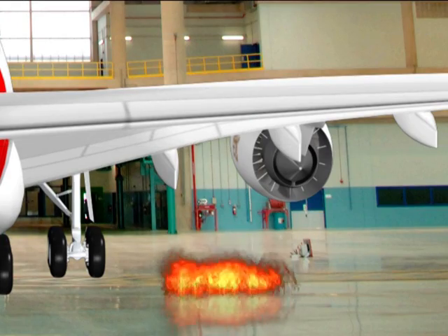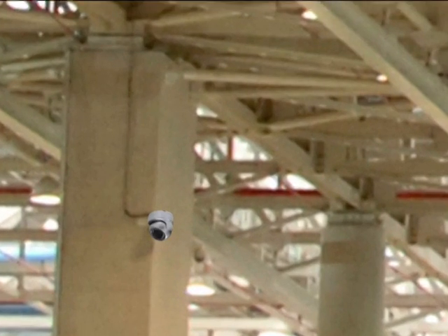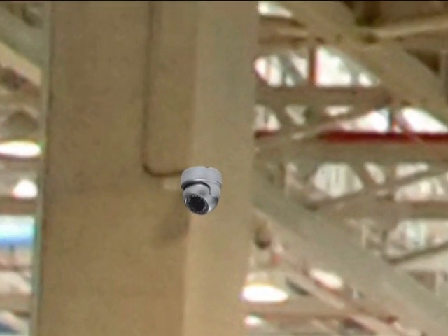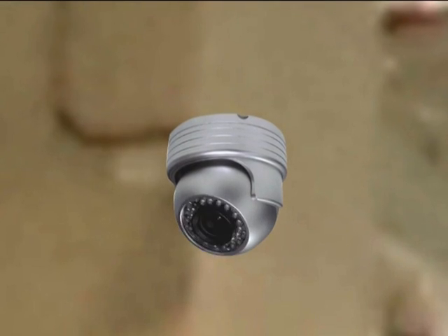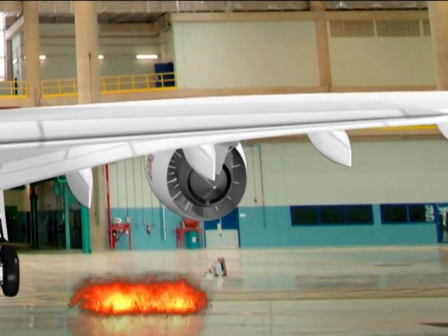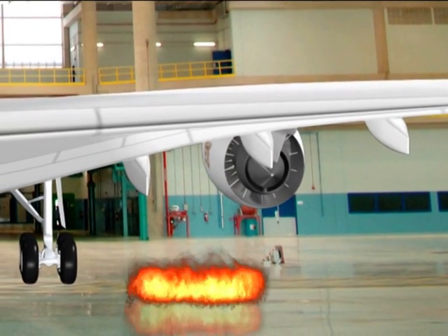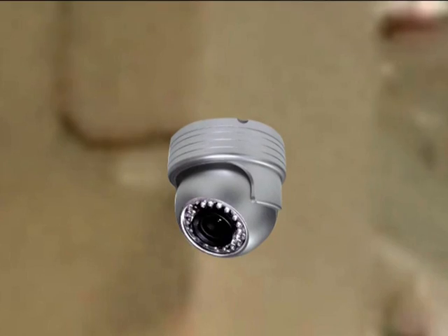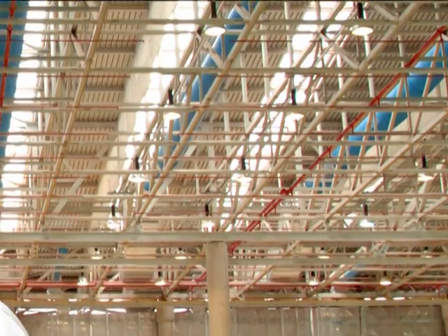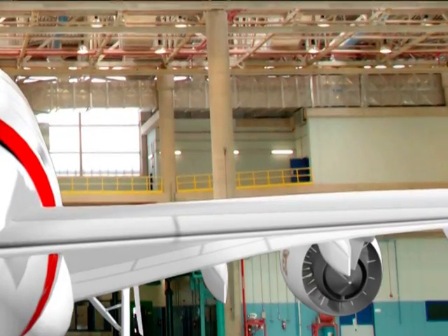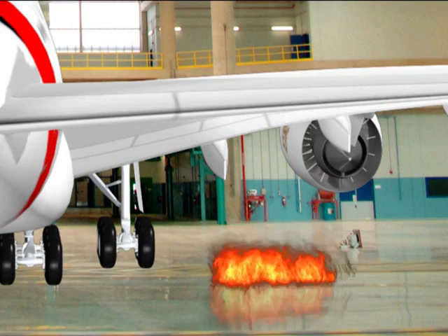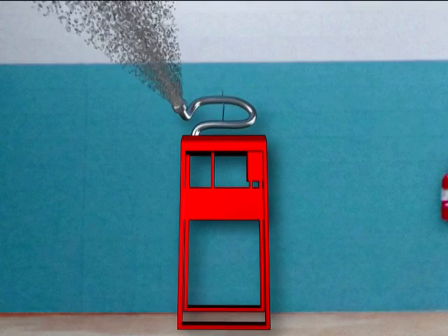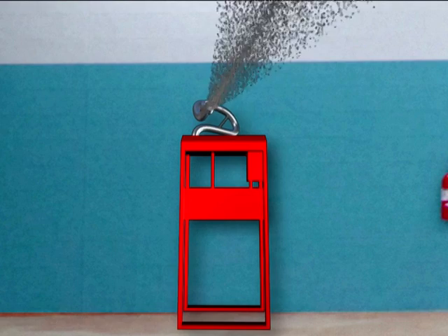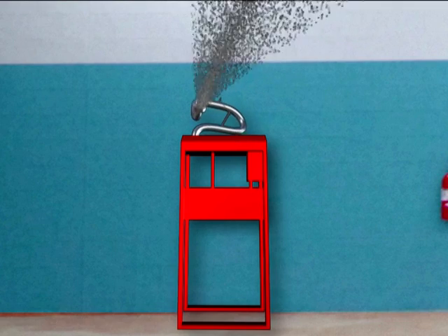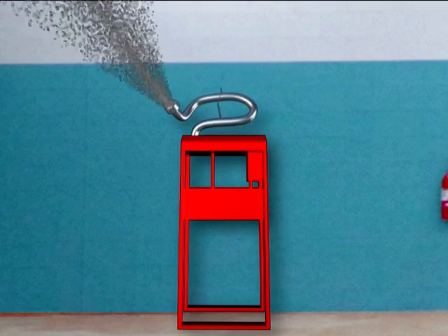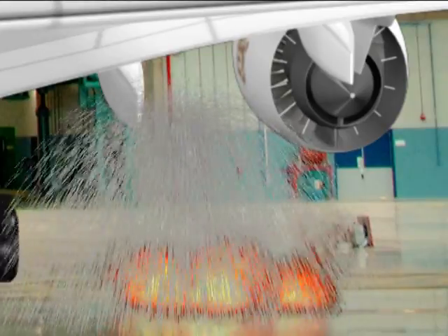This activates the second part of the deluge system, which is called the triple IR system. This system is made up of 3 infrared cameras that shoot pictures of the site of the fire reported by the coordinates given by the linear heat detection system. All this happens in milliseconds. Within 3 seconds of the linear heat detection system detecting the fire, the 2 oscillating monitor cannons under the high fire risk area under the wing of an aircraft start jetting water, swinging both ways in a wide arc.